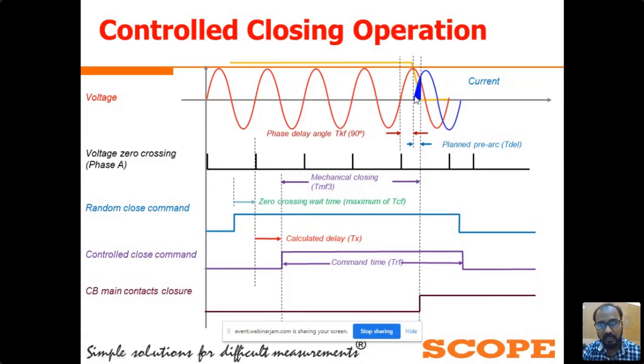The current starts very symmetrically. From this moment, the current starts to flow between the CB contacts, very gradually and very symmetrically. This is what we have achieved with control switching. We are targeting this point to operate the circuit breaker. In these control closing and opening operation examples, we have targeted the voltage peak points. In our next slide, we will see the target points that we take as a reference for the specific applications.